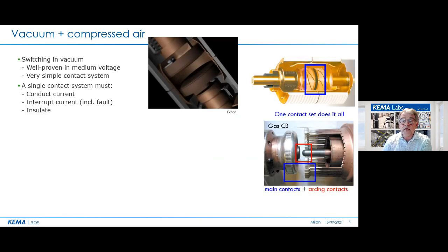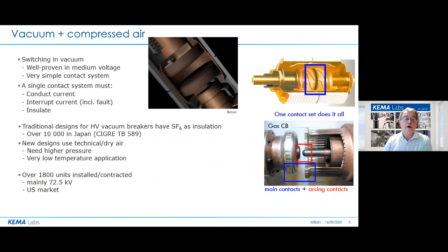Well, here you can see an enlargement of what the difference of the contact system of the 2 types of circuit breakers is. So you see the single contact set of the vacuum breaker, and below you see the main contacts and the arcing contacts of the gas circuit breaker. Well, some features of vacuum breakers: the traditional design of the high voltage type of vacuum breakers has SF6 insulation, and they are in wide use in Japan. Details can be found in Cigre Technical Brochure 589.